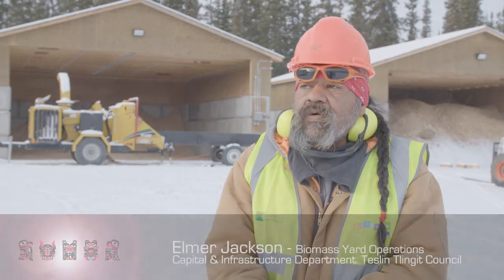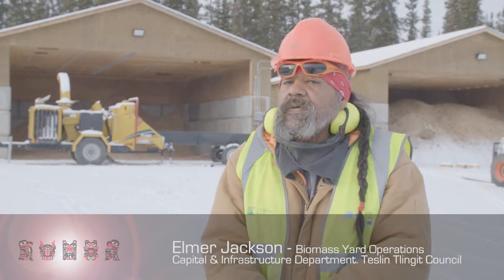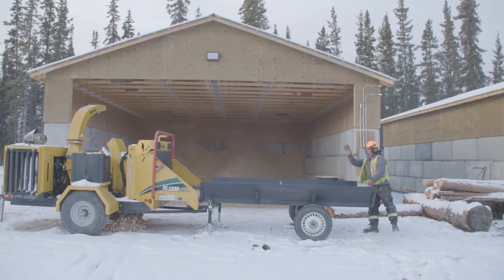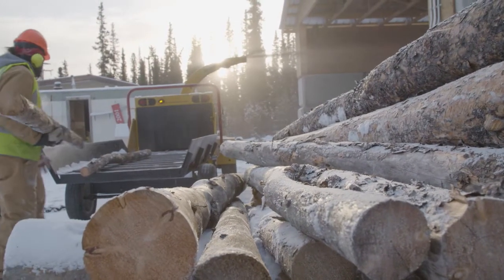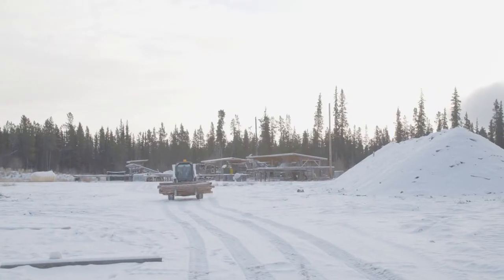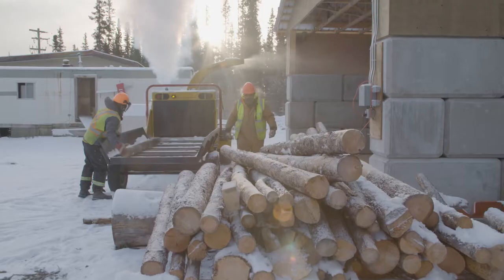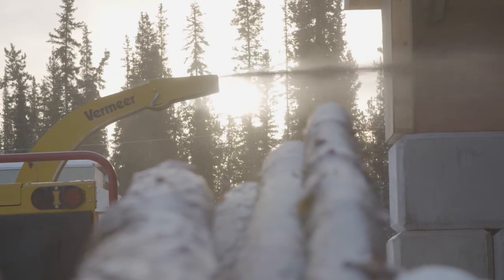We have 60 cord of waste material that we turned into chips. It turns into 30 cord of chips — one bay is full and we're just starting to fill our second bay. We've built an oversized concrete pad so the bucket never touches anything other than wood chips, which has really eliminated a lot of quality issues we've seen elsewhere. The yard will store wood inventory for one to two years to bring the moisture down, and once it's at about 20 to 30 percent moisture it'll be chipped and delivered to the energy centers as wood fuel.